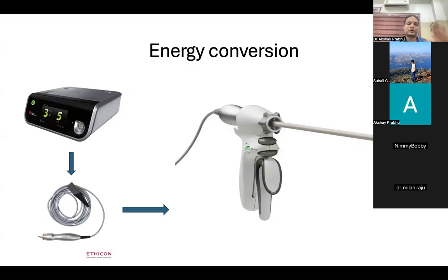So in this specific case, why is it called ultrasonic energy? You can see the generator here, which is written 3.5. This is the basic generator. We plug in this generator, and electrical energy is created inside it. That's why it's called a generator. It generates electrical energy. The same thing happens for bipolar and monopolar also. But the key lies here in this equipment. This is called the handpiece. Why is it called the handpiece, and why this peculiar shape? If you see this bottle kind of shape here, this is the device which plays the key role. This converts the electrical energy which comes from the generator into ultrasonic energy. So this is where the conversion happens.